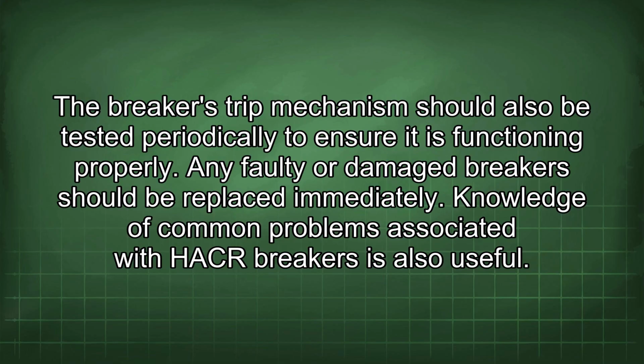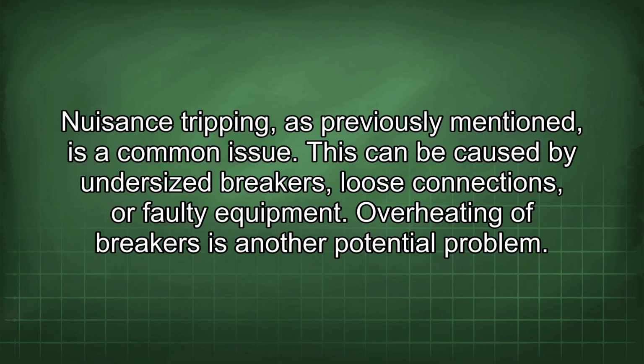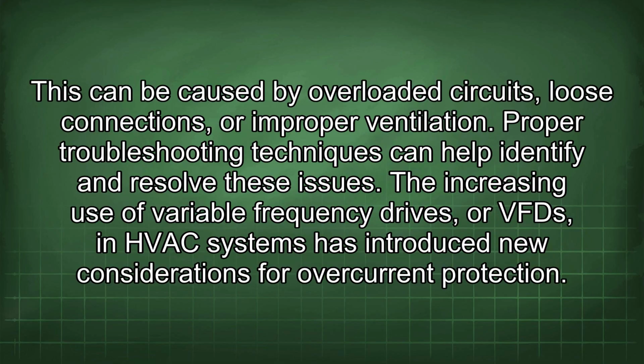Knowledge of common problems associated with HACR breakers is also useful. Nuisance tripping, as previously mentioned, is a common issue. This can be caused by undersized breakers, loose connections, or faulty equipment. Overheating of breakers is another potential problem. This can be caused by overloaded circuits, loose connections, or improper ventilation. Proper troubleshooting techniques can help identify and resolve these issues.